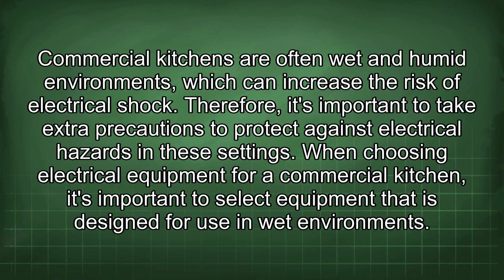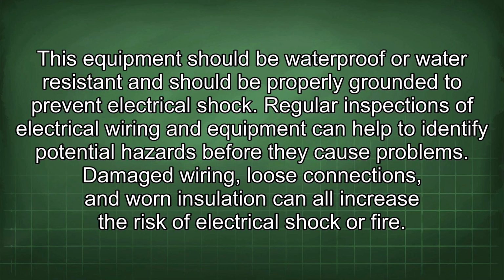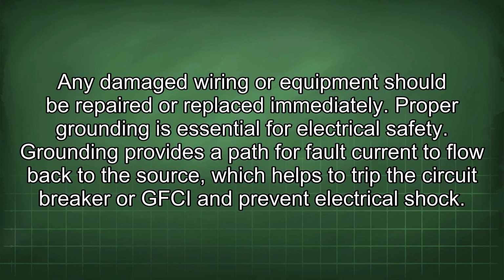When choosing electrical equipment for a commercial kitchen, it's important to select equipment that is designed for use in wet environments. This equipment should be waterproof or water-resistant and should be properly grounded to prevent electrical shock. Regular inspections of electrical wiring and equipment can help to identify potential hazards before they cause problems. Damaged wiring, loose connections, and worn insulation can all increase the risk of electrical shock or fire. Any damaged wiring or equipment should be repaired or replaced immediately.